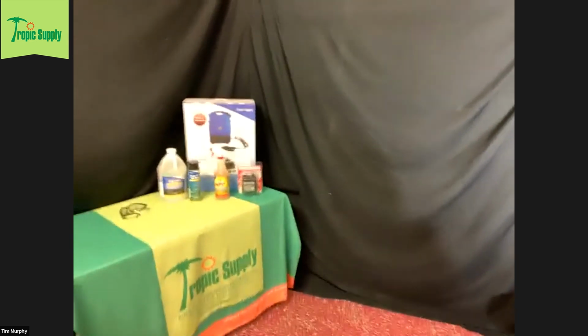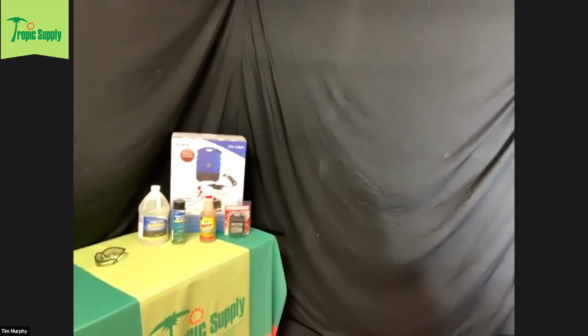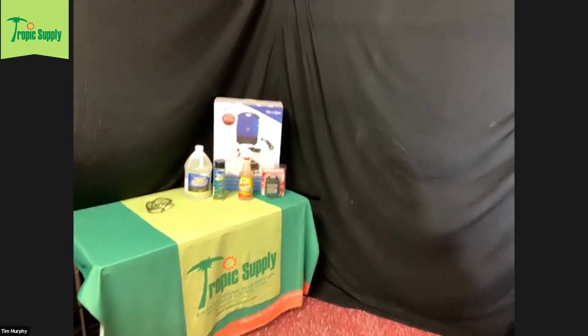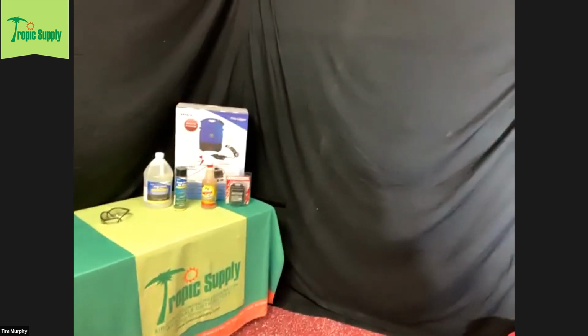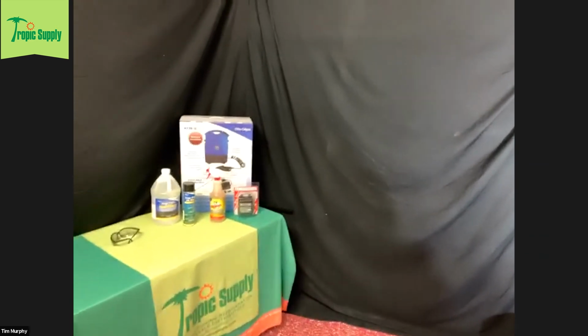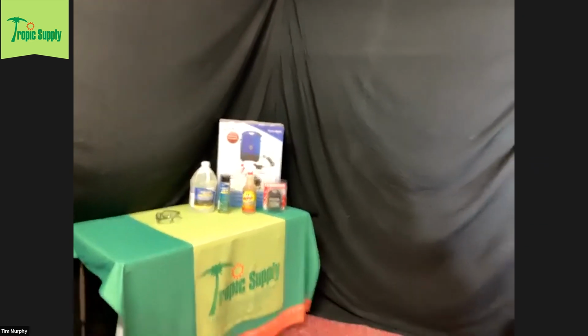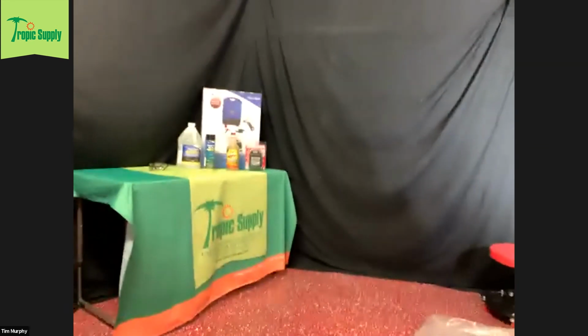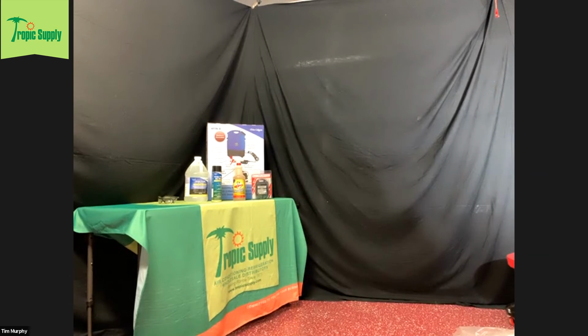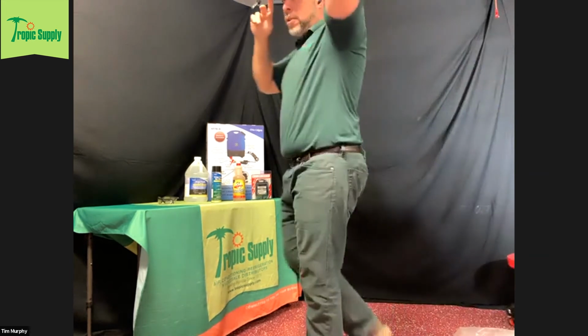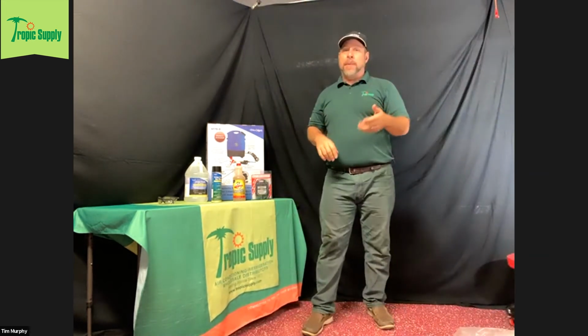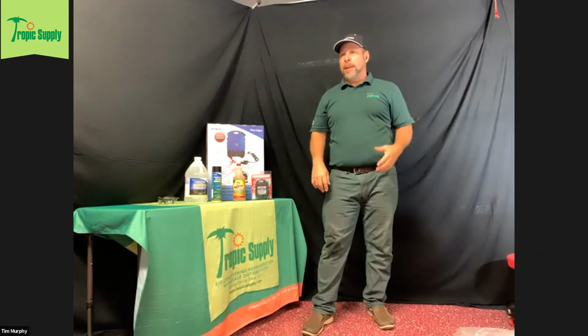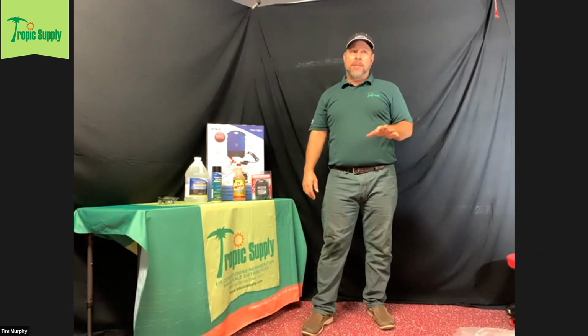I was just going to answer no to that question, but Todd is absolutely right. Where there's a will, there's a way, and by all means you can do a workaround on that system and put a relay in. What's great about Samsung is they've really thought about almost every situation a contractor is going to come in contact with, providing different relays and things to let you use different functions or shut certain things off. So it's great that you can use that, but when you put a UV light on, you don't want a blinking light. Just having it stay on is definitely recommended.